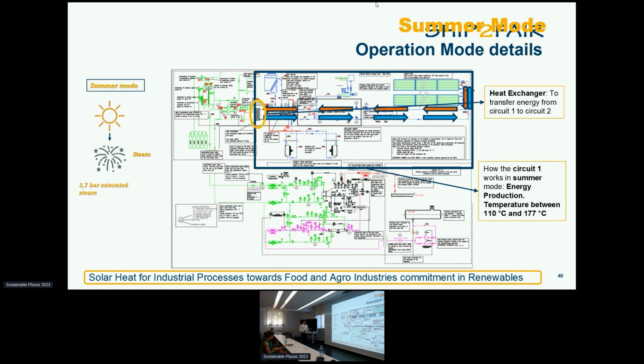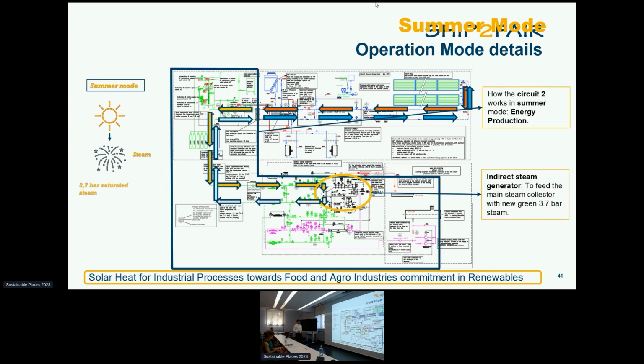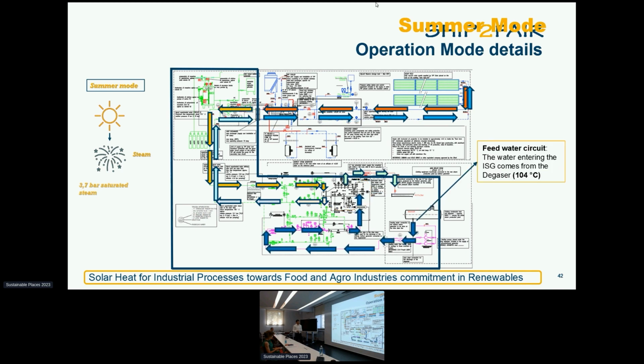In summer mode, we now have the flow of circuit 1 driven to the heat exchanger, and here we have a working temperature between 110 and 177 degrees. This energy is exchanged with circuit 2, which brings and fuels the indirect steam generator, producing 3.7 bar of steam. The indirect steam generator is fed by the water exiting the existing degasser at a temperature of 104 degrees.